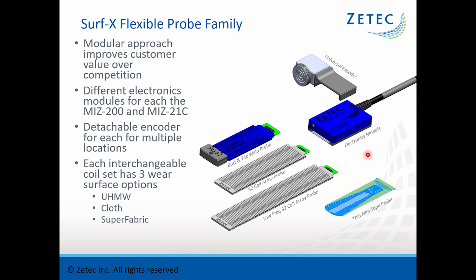There is a different electronics module required for either the MIZ-200 or the MIZ-21C, but the tape coil sets work with either instrument. Each coil set has three different wear surface options: UHMW, cloth, or superfabric. The UHMW is used in laboratories when you want to get very close to indications. The cloth wear surface is used to protect both the surface being inspected and the probe itself. The superfabric is a resilient fabric for use over very rough surfaces where scratching is not a concern.